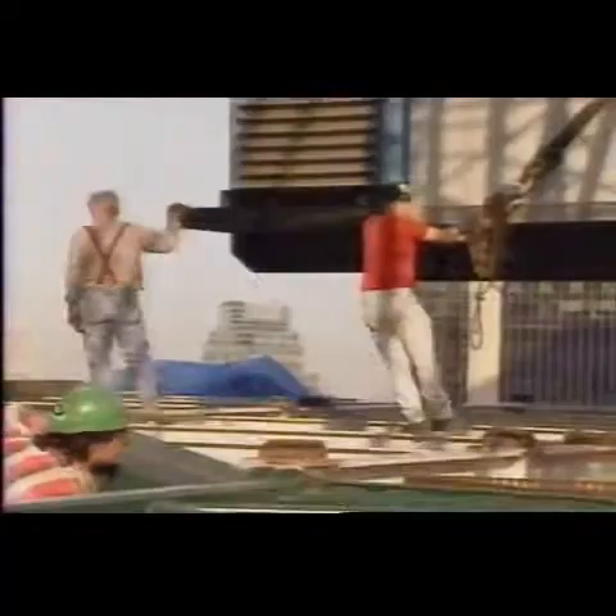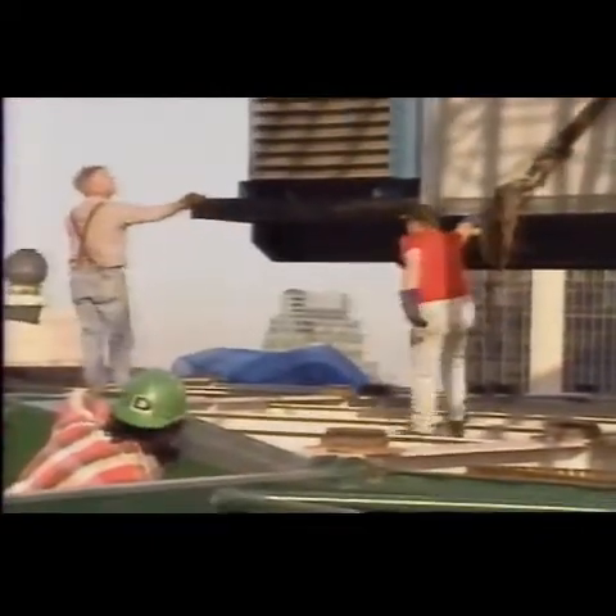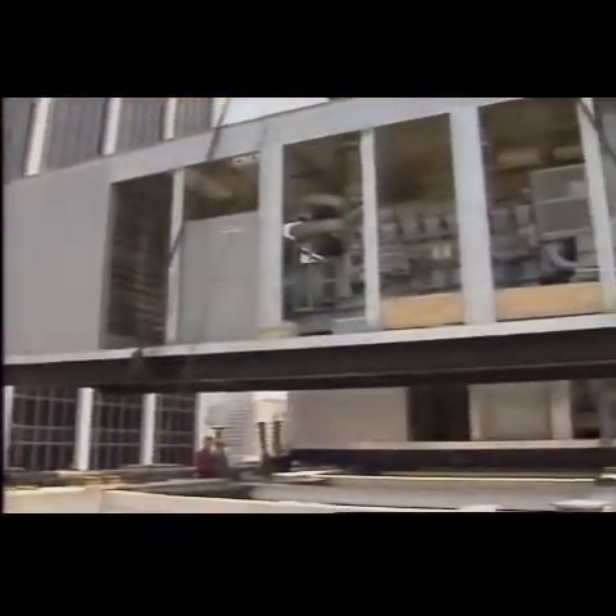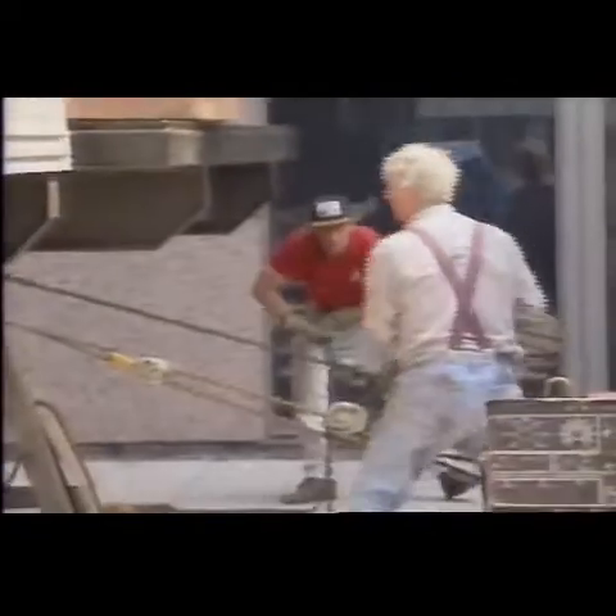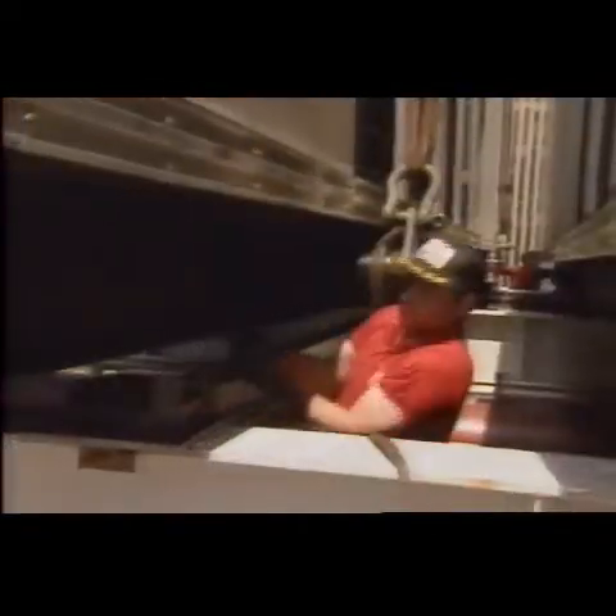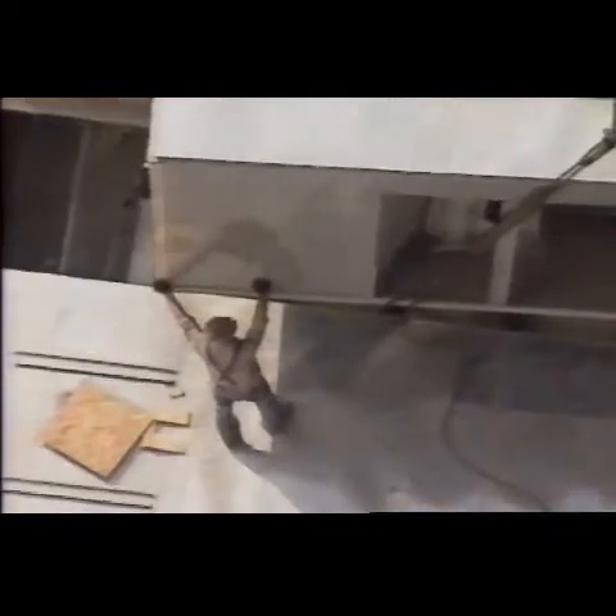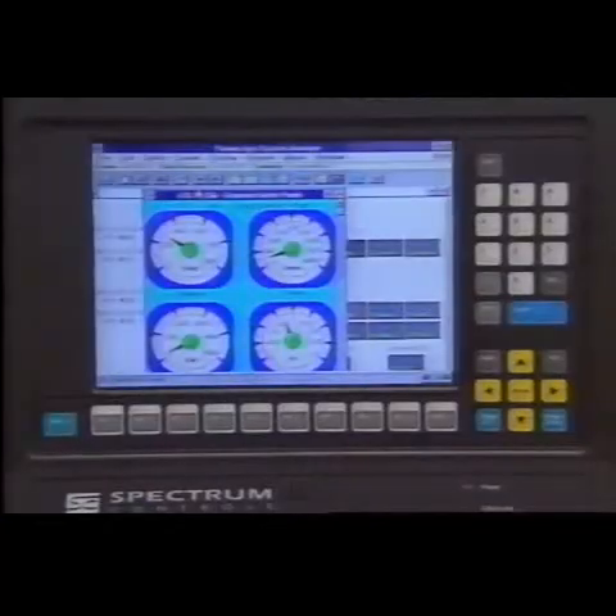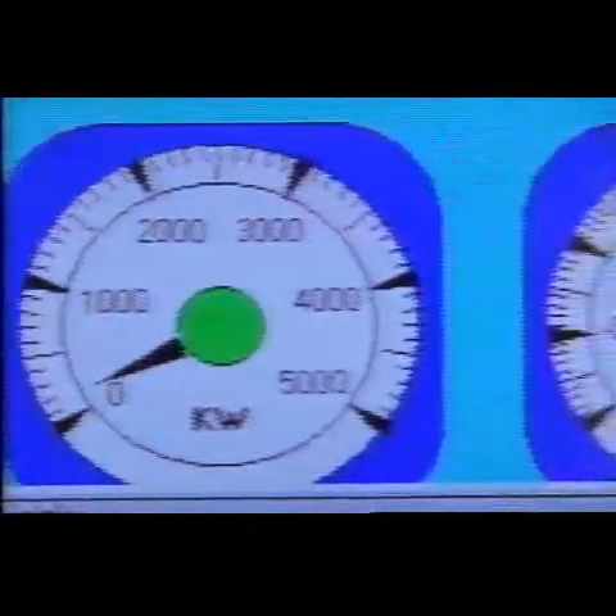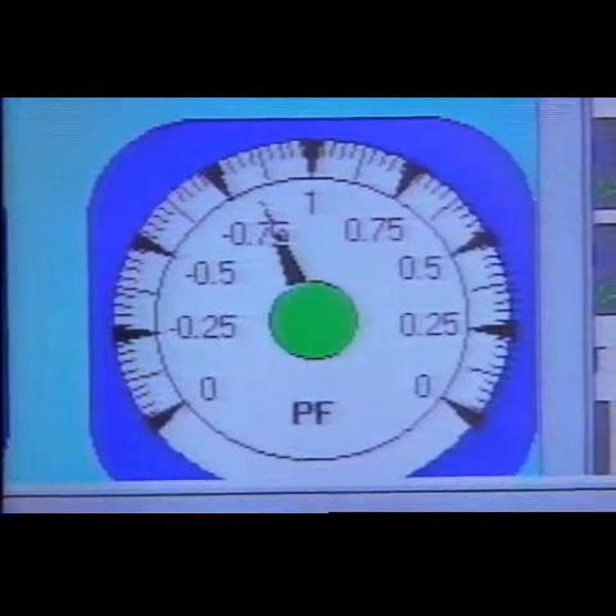Each unit was set on a dunnage steel platform, which was constructed on-site to support the weight of the plant. The units were slid into place one at a time and were then joined and sealed to become a single enclosure with easy access between the system generators and control systems. Installation, checkout, and commissioning took only 1 month. In total, Rudox's design, fabrication, and installation took 8 months from start to successful final installation and commissioning. Coordinated engineering, programming, and fabrication enabled site construction and system installation to be completed with minimal interruption of the building's normal functions.